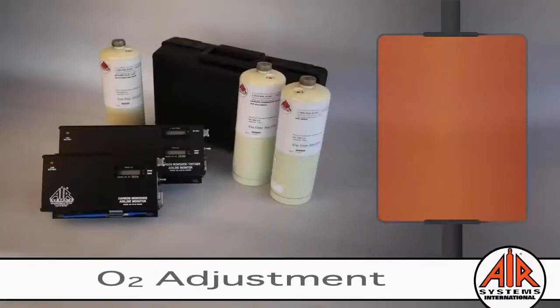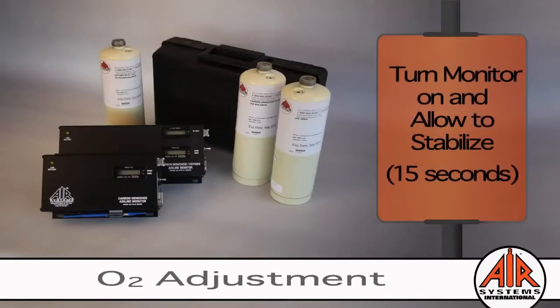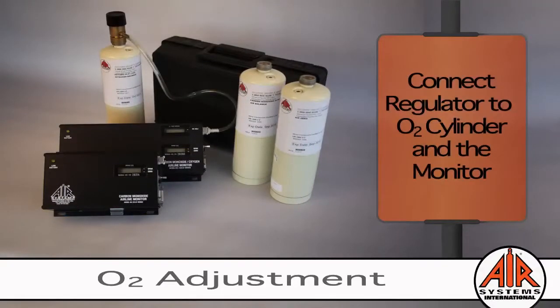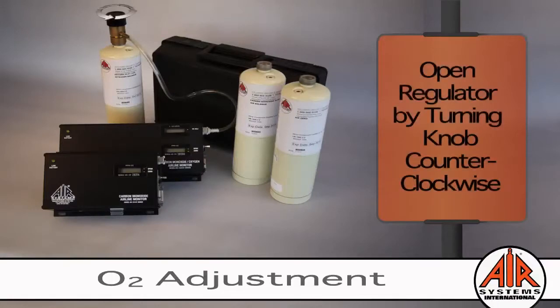If you have the monitor with the oxygen option, we have one final phase of calibration, and that would be the O2 adjustment. Make sure the monitor is turned on and has been allowed to stabilize for at least 15 seconds. Connect the regulator to the O2 cylinder and the monitor. Open the regulator by turning the knob counterclockwise.